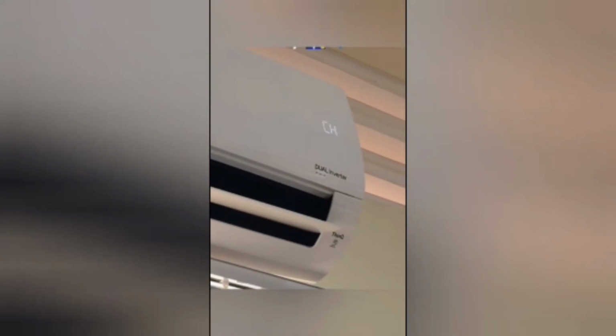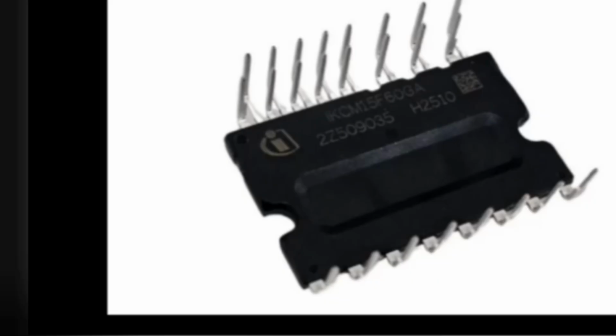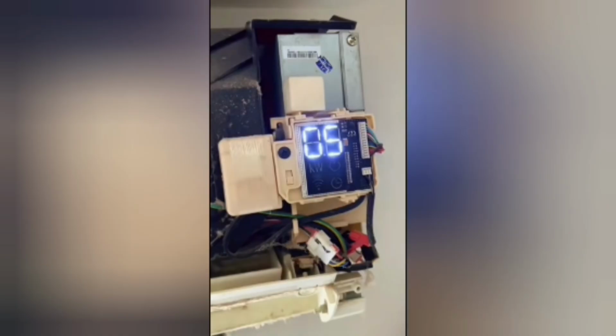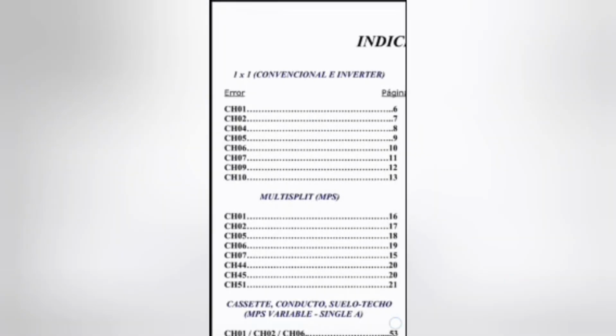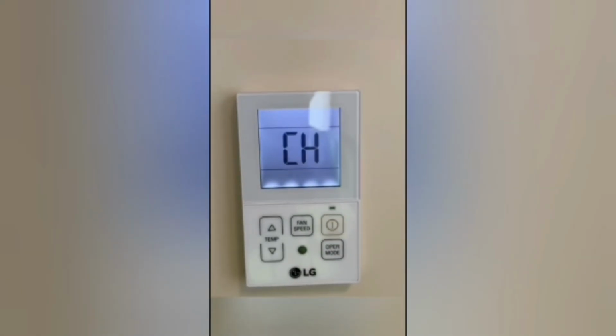In addition, when an inverter air conditioner throws this error at you, which is the communication error, it restarts by itself, or the compressor wants to start and it cuts off, do not go directly to change the motor, because many times the culprit is only a dried up capacitor. This capacitor already lost its capacity and lets all that noise pass through.